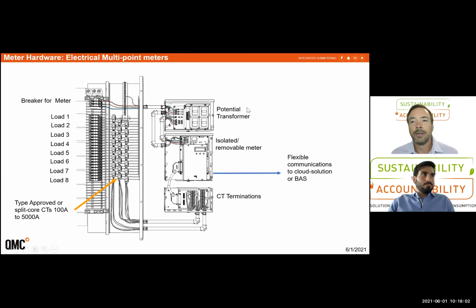So I just wanted to go a little bit further here on these multi-point meters, because they are so common in commercial, institutional, and multi-res properties these days. This shows 8 breakers or 8 loads on a distribution panel where we've put current transformers on the A, B, and C phase of each load. What this allows you to do is monitor 8 meter points, or up to 24 current transformers, on one electrical meter. That allows for massive cost savings, easier installations, and you're getting a ton of data out of these systems in the end.